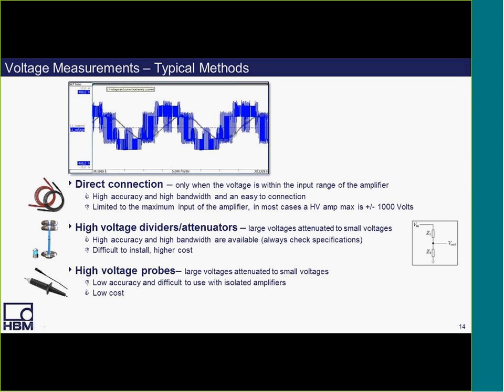Here's a list of some of the typical methods used to connect high voltages. We'll also talk about some of the currents as well for making measurements. Each method has its pluses and minuses. Of course, a direct connection is one of the easier connections to make. The plus there is high accuracy and high bandwidth. Unfortunately, you're limited to the maximum input of the amplifier, and in most cases, a high voltage amp will have a maximum of about plus minus 1,000 volts.